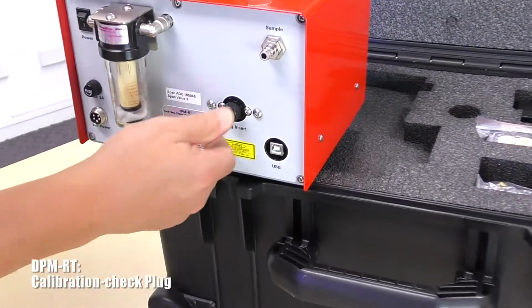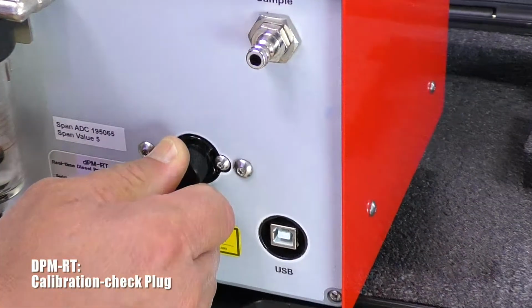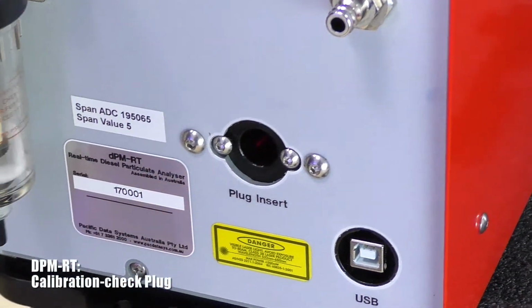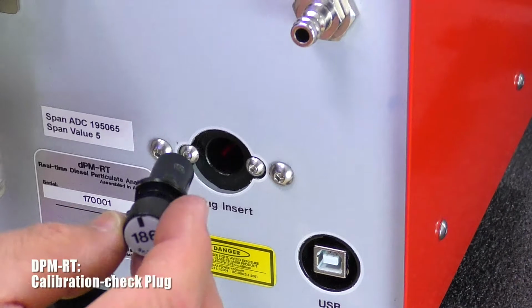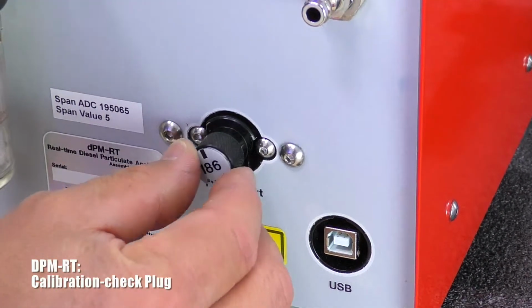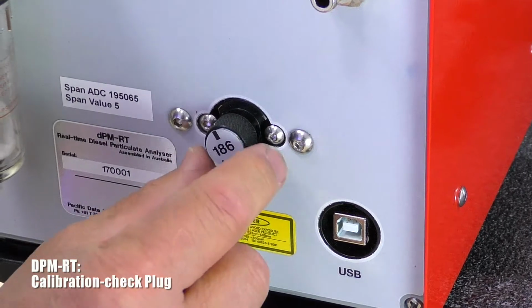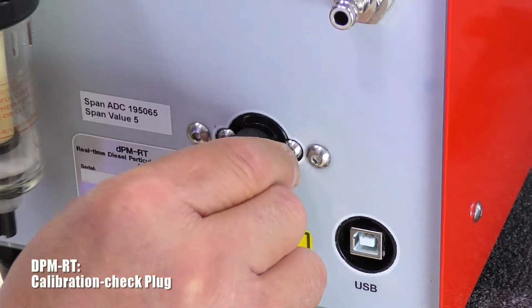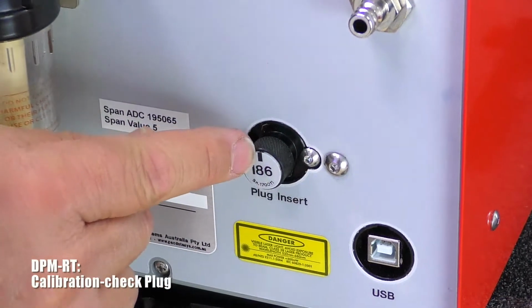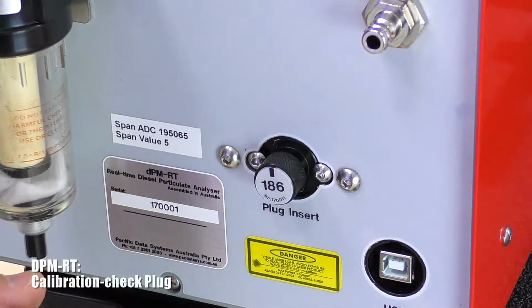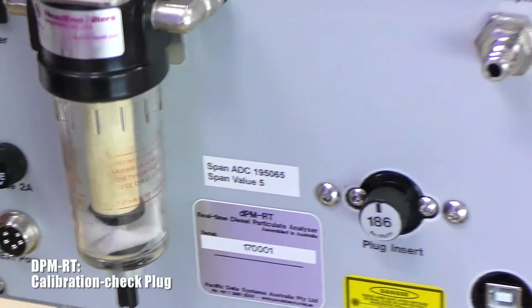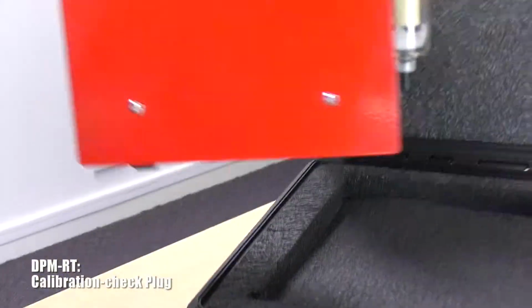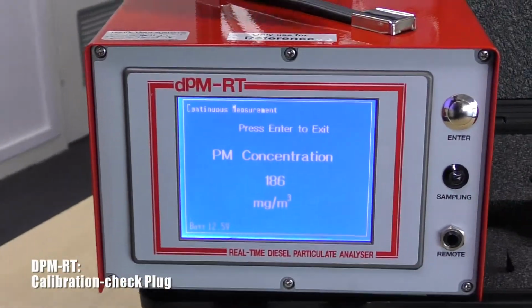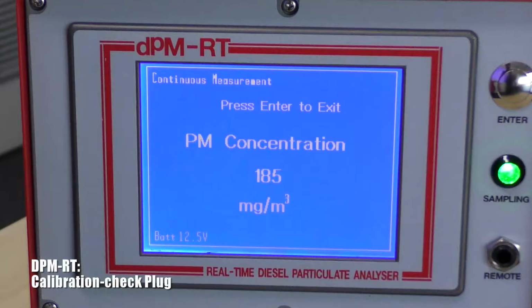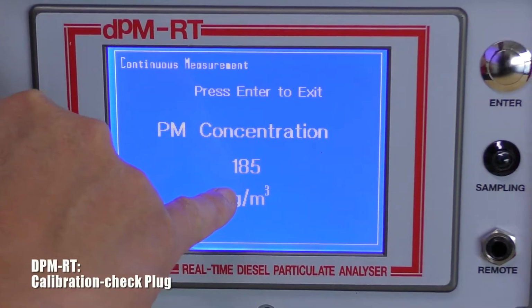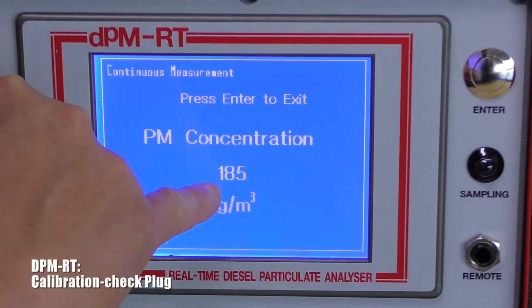You remove your plug insert from the instrument, rotating anti-clockwise, and then inserting your calibration check plug into the plug insert, and then rotating it slightly to the right, clockwise, ensuring that the black indicator is facing in the upwards direction. When you turn the instrument around, the value on the calibration check plug should be within plus or minus 5% of the display value on the screen.